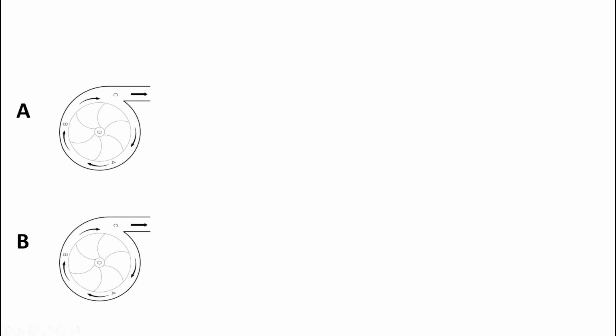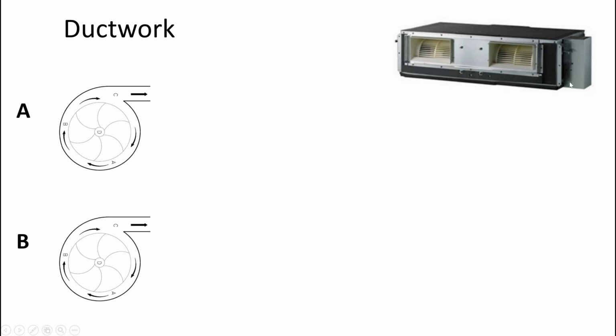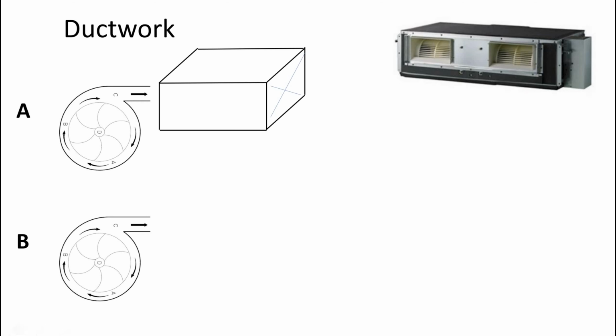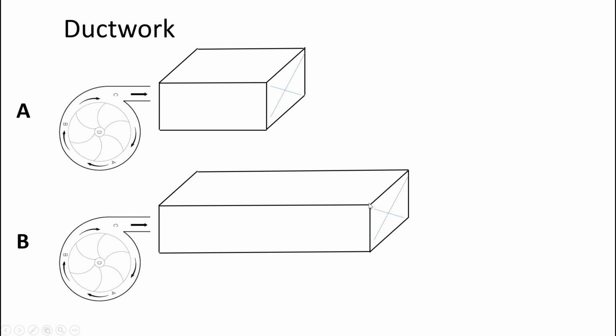Okay, this is clear. Let's talk about ductwork now. Again, let's say we have two cases, A and B. These two fans in two cases represent the fan in the LG indoor unit. It is a ducted type indoor unit, and it is expected that it will be connected to ductwork. Let's say we connect the same indoor unit to two different ductworks, ductwork A and ductwork B. Ductwork B is a little bit longer than ductwork A. Ductwork A has less volume inside the duct in comparison with ductwork B.